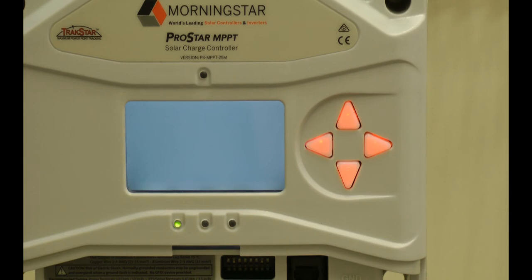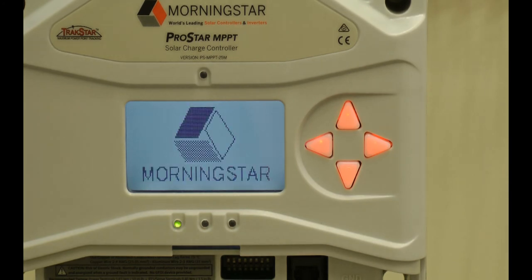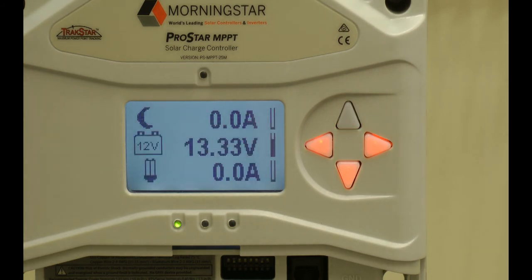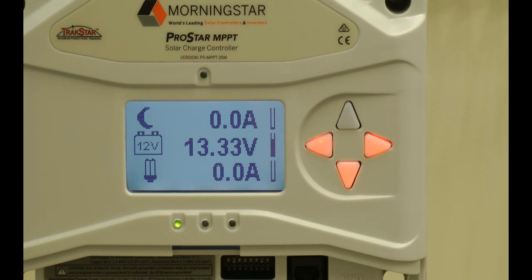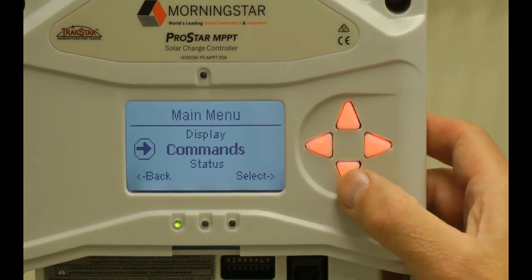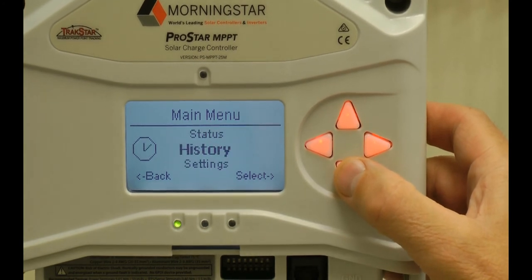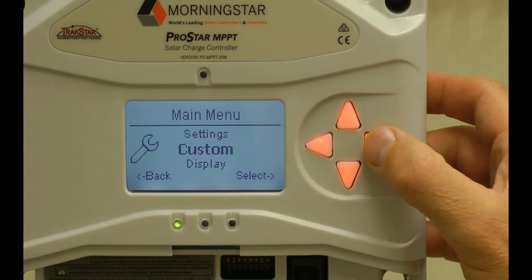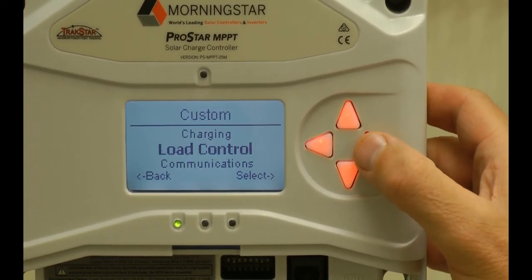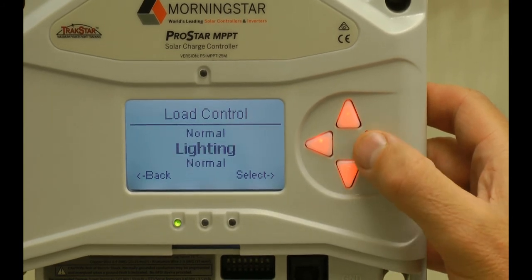While waiting for it to come on, I have the menu map available so I can make sure I understand where I'm navigating to. I also have my lighting control programming document that I created earlier so I can follow along as I do the programming. Using the down arrow, we will hit the main menu, continue down until we hit custom, use the right arrow to select custom, go to load control because that's where the lighting is, and select lighting.